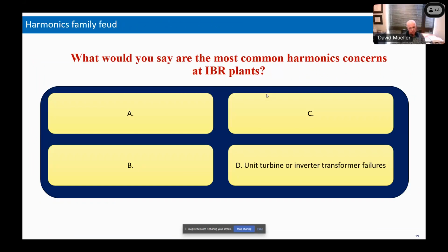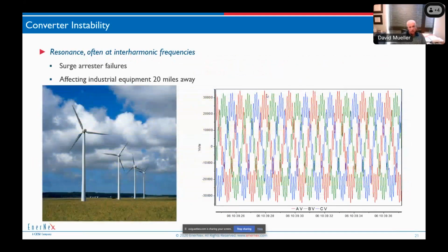All right, so now let's move on to the next one. What is the next one that I call out as a common harmonics concern? Converter instability. So the story is always very similar on these projects. The project was running just fine. Then the vendor decided to push a new version of firmware into the controls of the wind turbine. And following that, the main transformer in the substation started making strange noises. Capacitor banks started tripping, other problems started occurring.